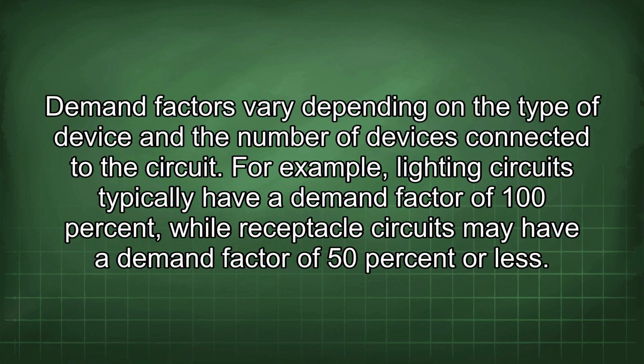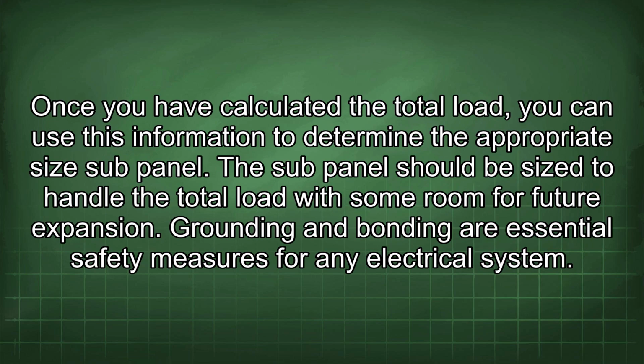Demand factors vary depending on the type of device and the number of devices connected to the circuit. For example, lighting circuits typically have a demand factor of 100%, while receptacle circuits may have a demand factor of 50% or less. Once you have calculated the total load, you can use this information to determine the appropriate size sub-panel. The sub-panel should be sized to handle the total load with some room for future expansion.